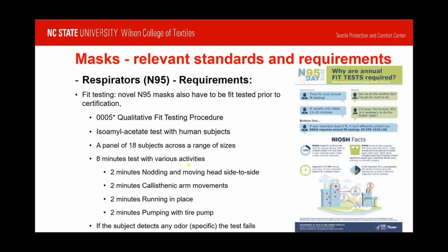18 subjects must be tested across a range of sizes from, let's say, small to extra large. And it's an 8-minute test with 2-minute activities, pretty much movement of the head and the body, because all of that will cause challenges to that seal of the mask to the face. And hopefully the mask is designed good enough to ensure that no breakage of seal exists and there's good protection to maintain their 95 protection level.